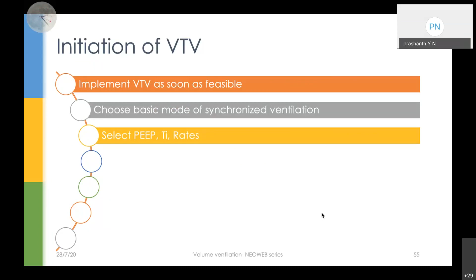And the most important thing, ensure the flow sensor is calibrated and functioning properly. When I said the microprocessor is the brain of your ventilator, this flow sensor is the sense which actually gives feedback to your microprocessor. If your flow sensor is not working, then your brain won't work. As simple as that. So you need to make sure your flow sensor is calibrated and functioning properly to pick up the flows and volumes, and then VT.